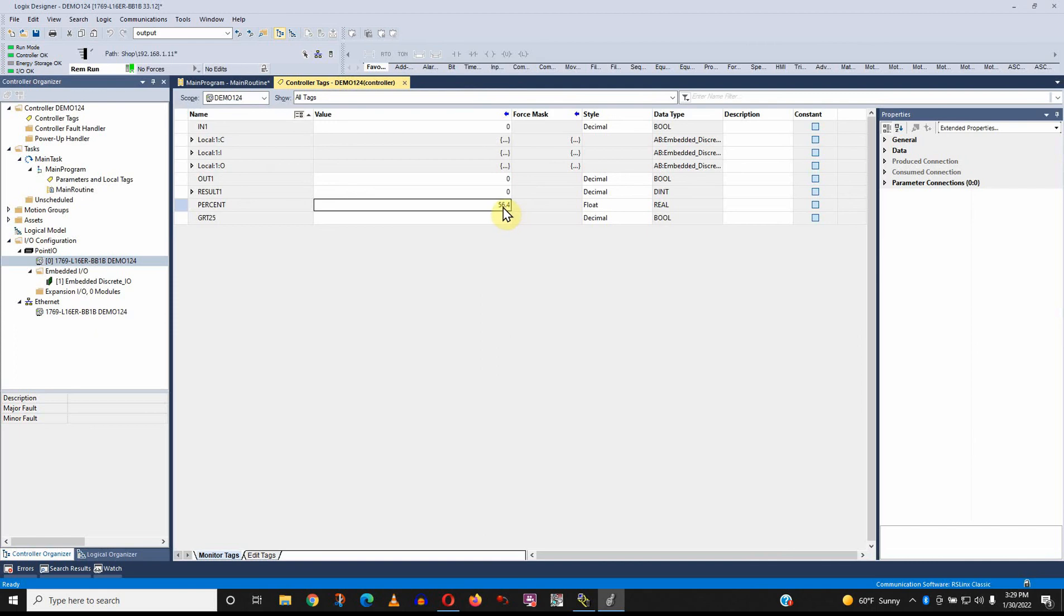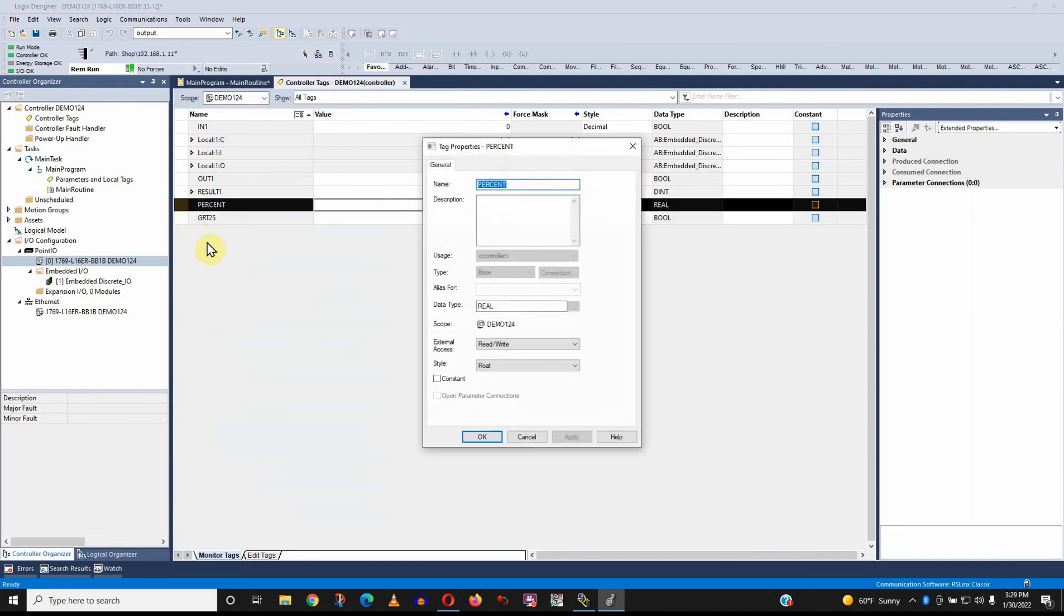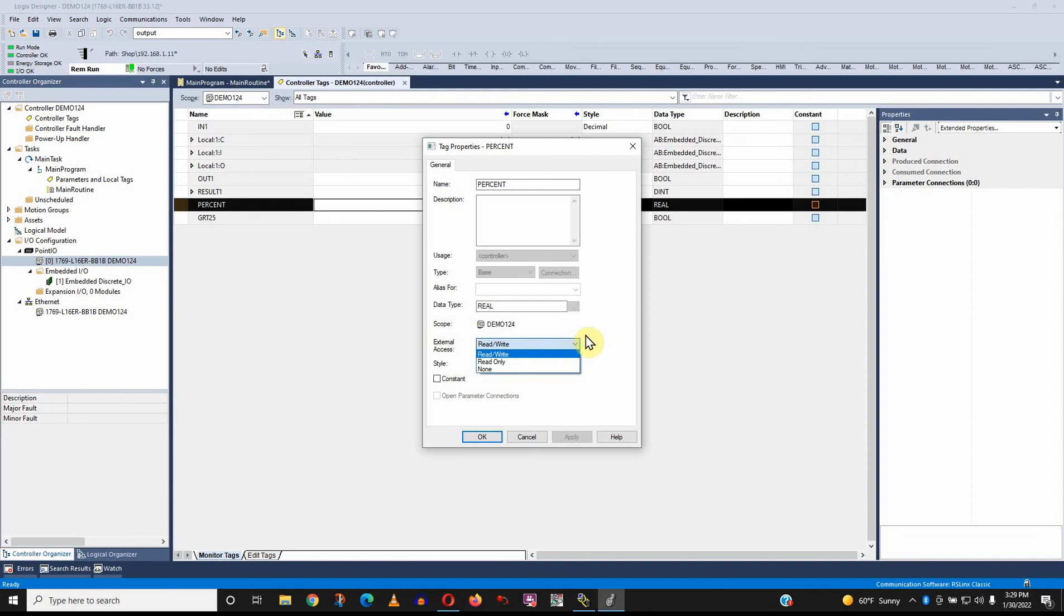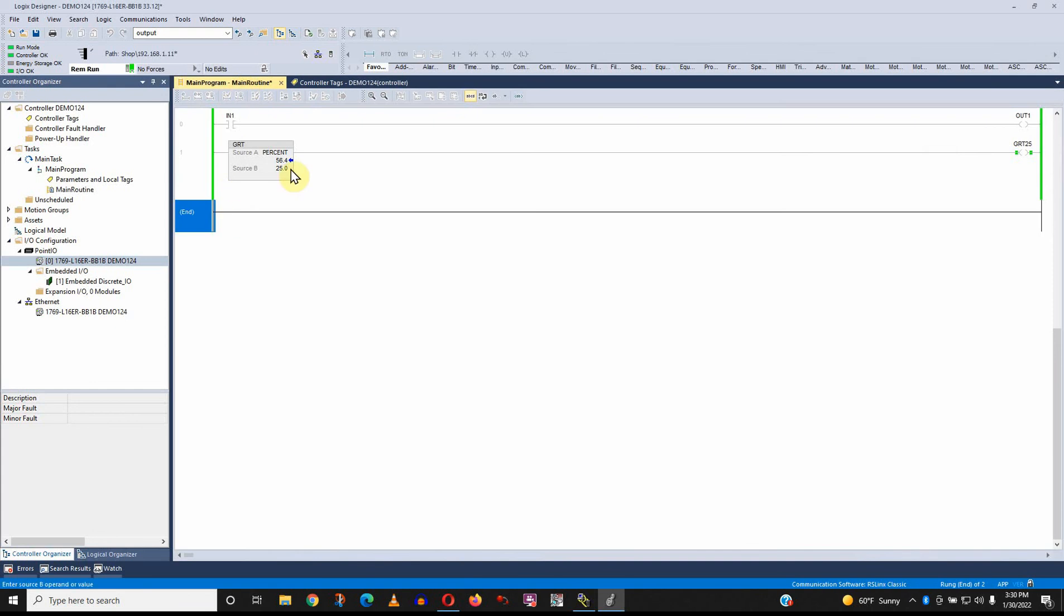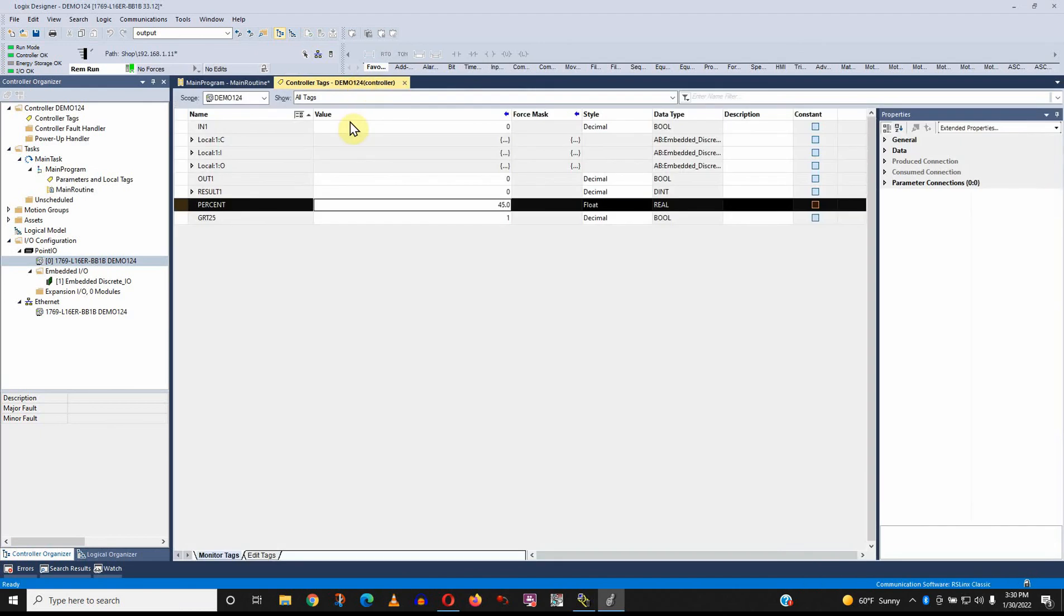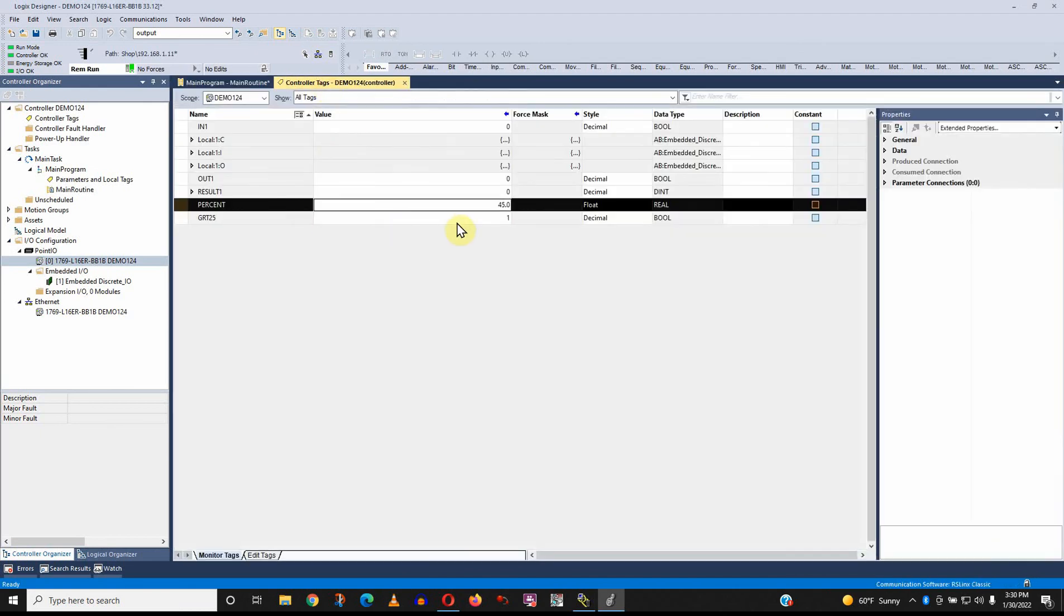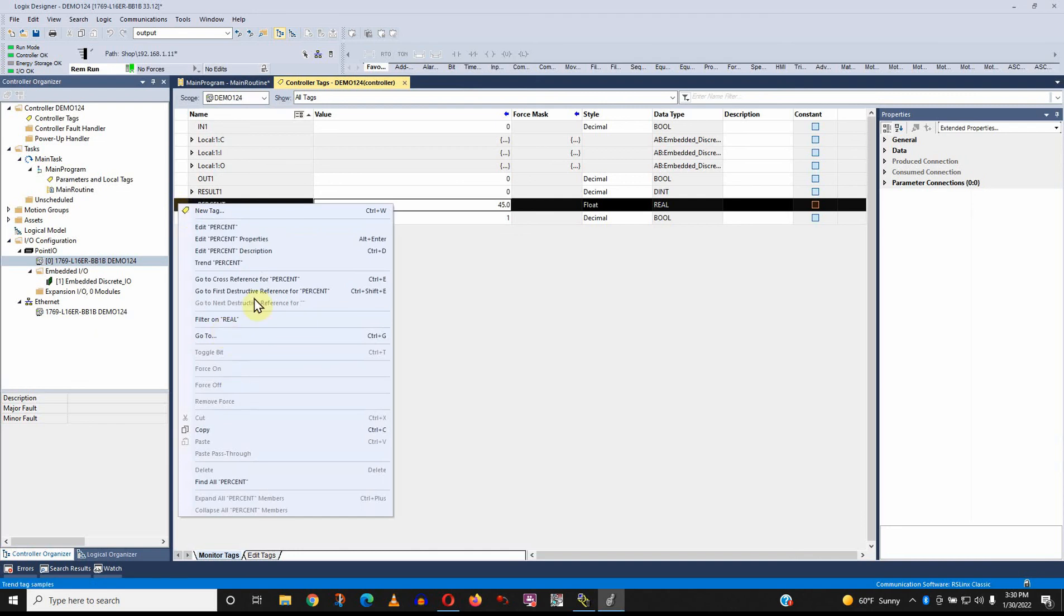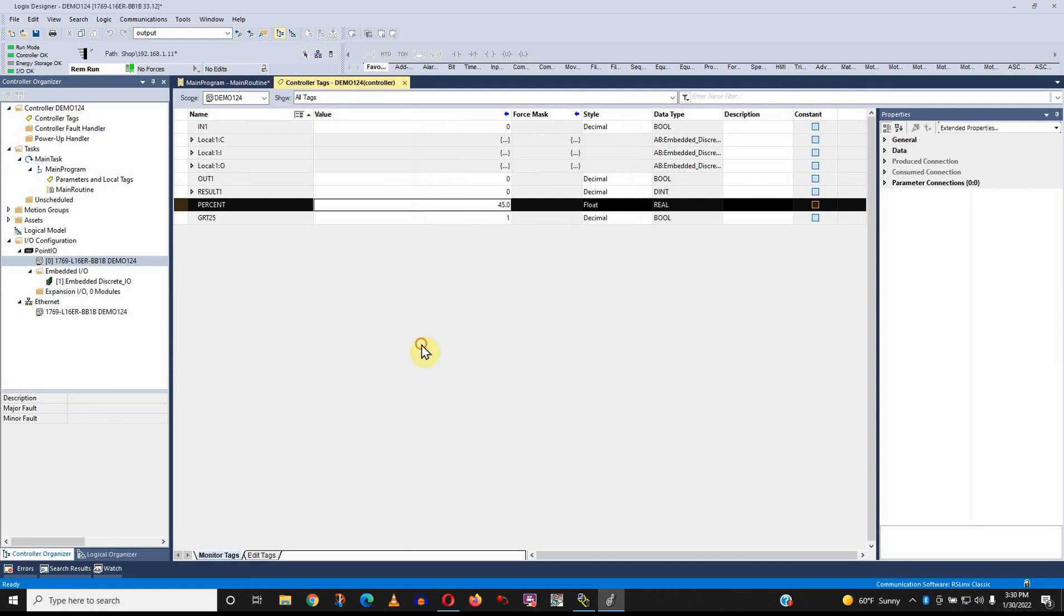So a couple of things I can say about this. The percent value 56.4, it can be modified internally or externally. If I right click on this and go to properties, you can see that I left the read write capabilities open. So if I have an HMI screen somewhere like an operator interface, that person could change that number. If I don't want that, I could make it read only, which means that you can't change it externally. You can change it within the program. Like if I make that 45 percent. So I can change it, but only within the program. Read only means I can show it on the screen, but I can't change it remotely. Obviously, that makes a lot of sense. A tank percentage, you don't want to change that. That comes from a sensor somewhere and got to leave that alone.